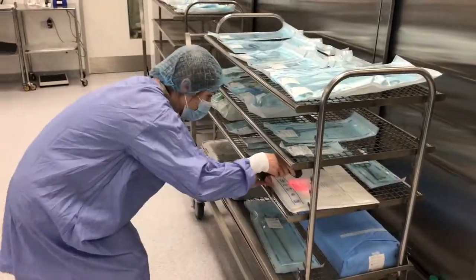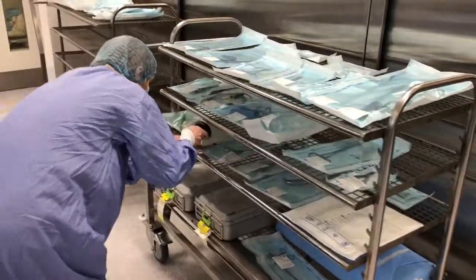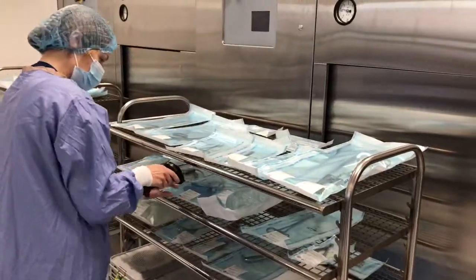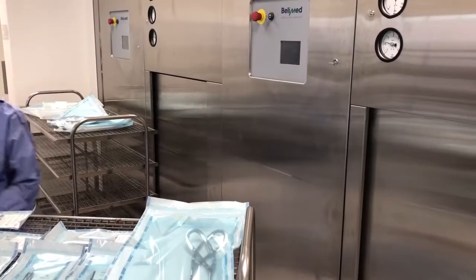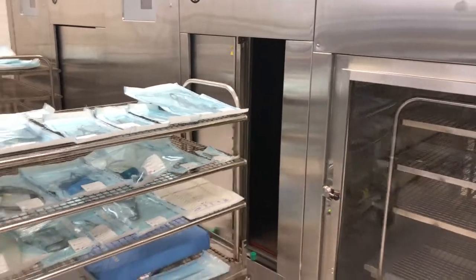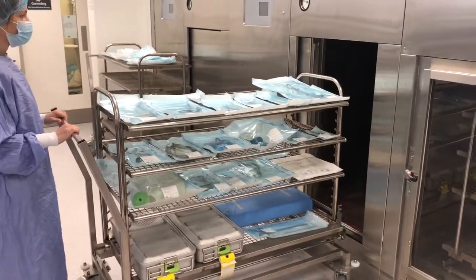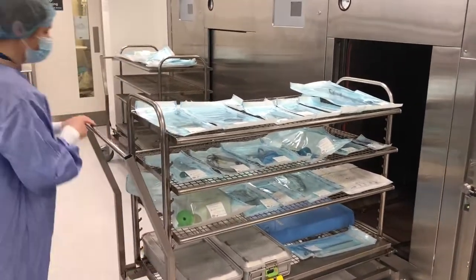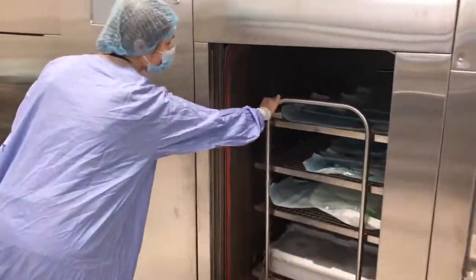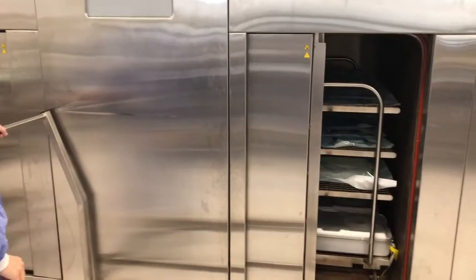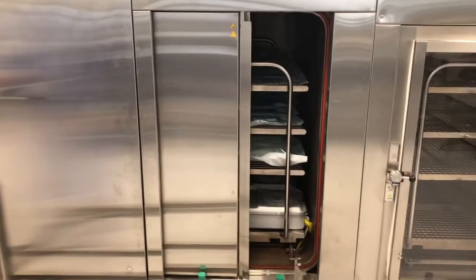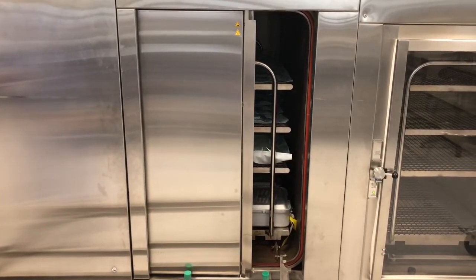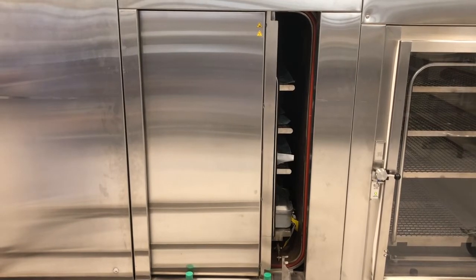Once ready, the equipment continues its journey by being scanned into an autoclave ready for steam sterilisation. An autoclave is like an oven which sterilises equipment to a high temperature. The equipment is loaded onto special trolleys and wheeled to the autoclave. The door is closed and the autoclave is activated. Sterilisation cycle takes approximately 50 minutes, and like the wash process, it must attain a specific temperature for a certain time. In this case, between 134 to 137 degrees centigrade for a minimum of 3 minutes.